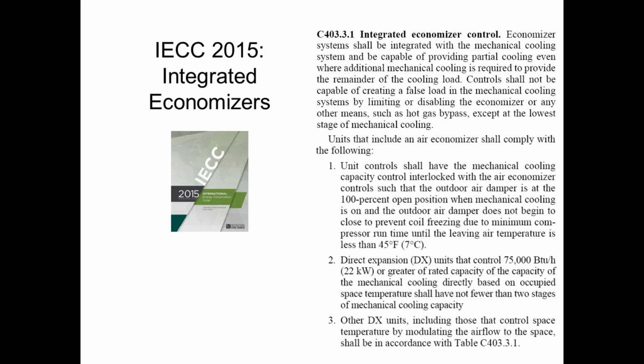So if I'm trying to get down to 55 degree supply air and it's only 67 degrees outside, obviously, the best I could possibly do would be 67 degrees supply air plus fan heat. So I'm not going to get there. So my damper is going to go wide open. I'm going to get 67 degree air, which is better than the 75 degree return air I would have gotten. But I'm going to have to turn my compressor on to take it the rest of the way. So an integrated economizer is required by code.